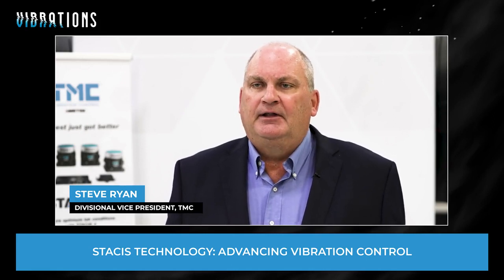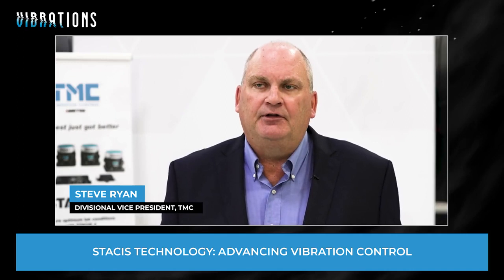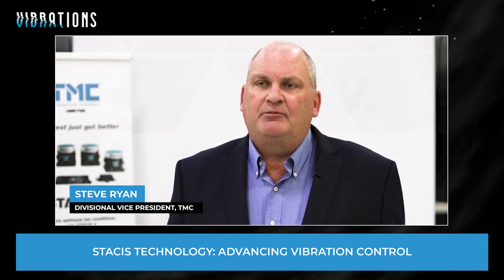So that means the sites need to be made quieter by vibration isolation systems offering more attenuation than was available in the past, and that's what STACIS 4 is able to do. Really, the gold standard for vibration isolation from STACIS historically was about an order of magnitude at 2 hertz vertically and horizontally, about 20 dB. And with STACIS 4, in some cases, for some of our installations, we've been able to get 2 or even 3 orders of magnitude of attenuation at 2 hertz vertically, and about 2 orders of magnitude attenuation horizontally.